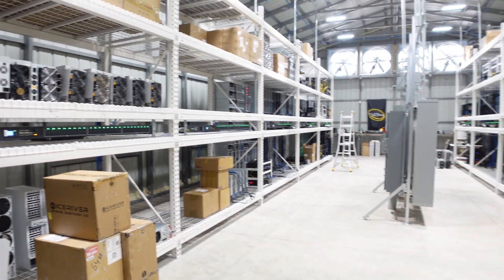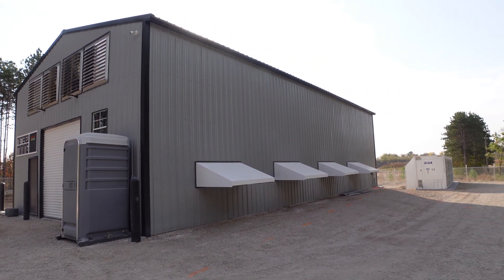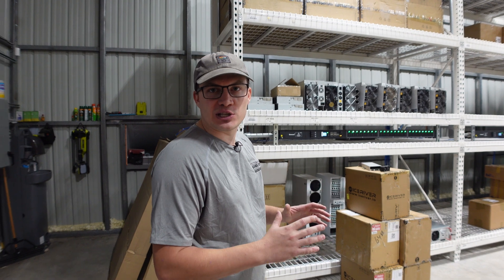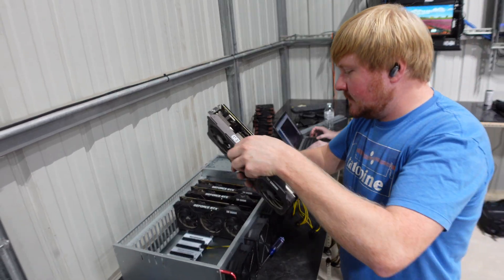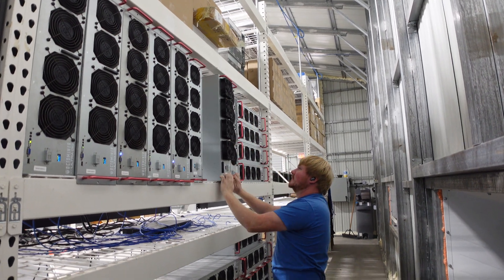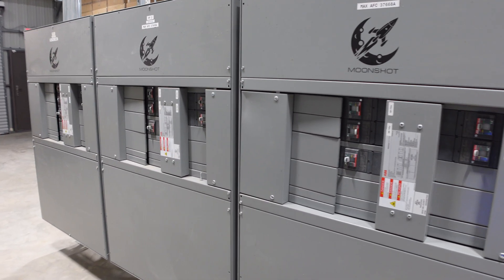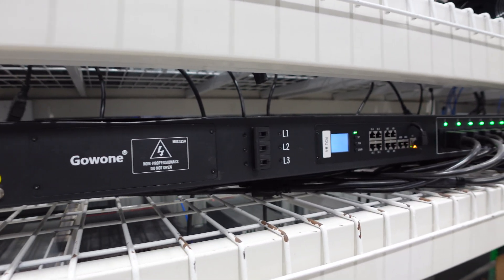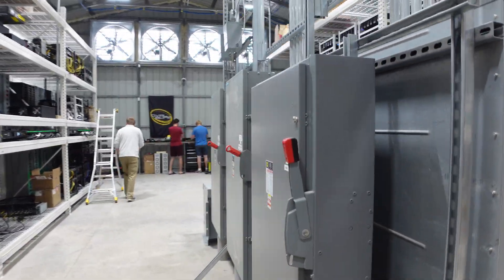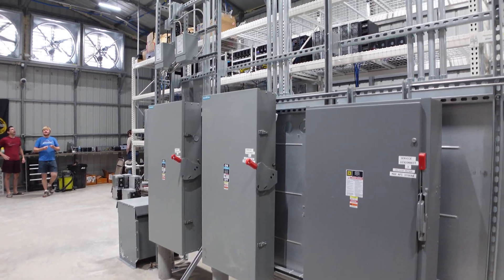You're seeing a lot of room for expansion because AI data center rigs are coming in. This building is a 1.2 megawatt building, and we have capability of doing four to five megawatts on site. This entire building is spoken for. In the middle of the building we have 600 amp moonshot panels, 125 amps per breaker going up and over down to our custom made PDUs. On the reverse side of the distribution panels, we have our breakers, disconnects, and step-down or step-up transformers for our fans and outlets.